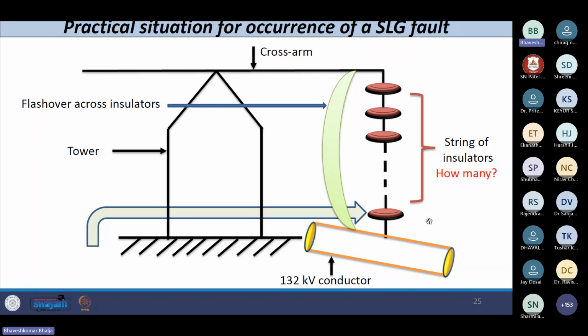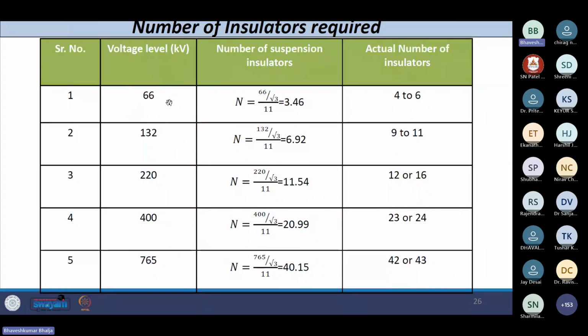For the different voltage levels, 66, 132, 220 and 400 kV, the number of insulators required is shown here. I have written a range, not an exact value, because you have to consider a factor of safety. You also have to take the integer value: if the calculation gives a floating value, you have to round it to an integer, considering the factor of safety.